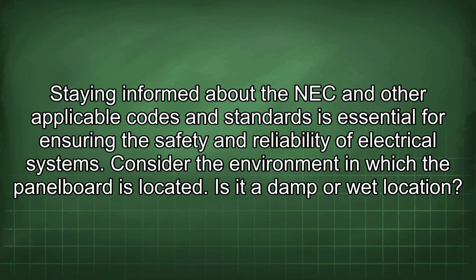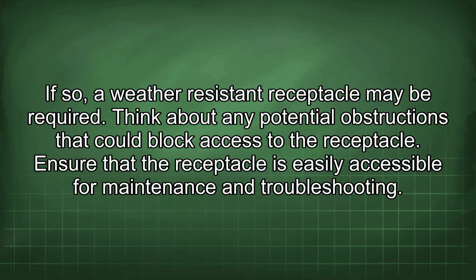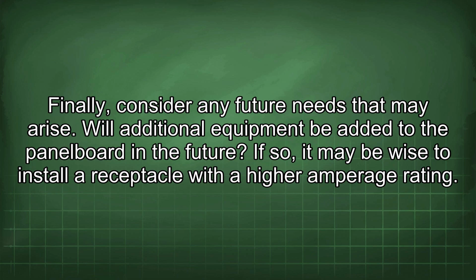Consider the environment in which the panel board is located. Is it a damp or wet location? If so, a weather-resistant receptacle may be required. Think about any potential obstructions that could block access to the receptacle. Ensure that the receptacle is easily accessible for maintenance and troubleshooting. Finally, consider any future needs that may arise. Will additional equipment be added to the panel board in the future? If so, it may be wise to install a receptacle with a higher amperage rating.